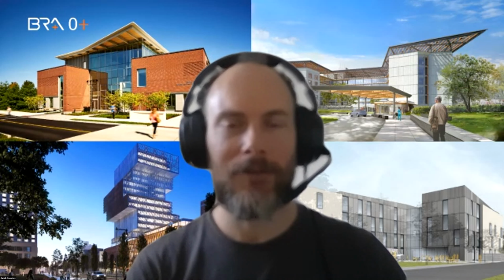So we've done a couple of 50,000 square foot buildings - actually, a couple of them are in the pictures behind me. We're typically in the range of 20 to 30 boreholes, 500 feet deep. But those are for classroom buildings or lab buildings, so they're more intense.